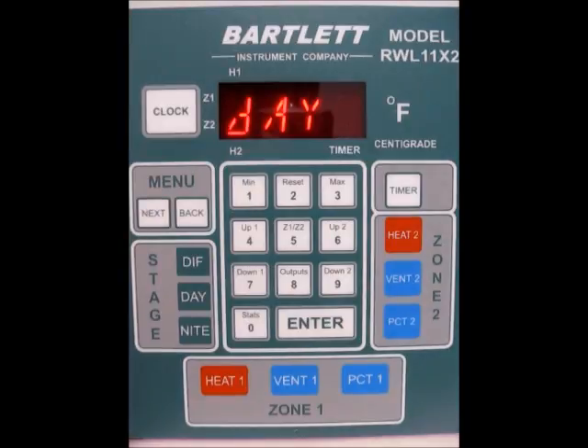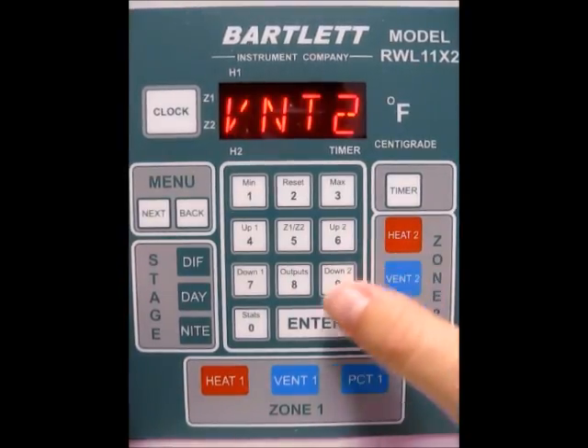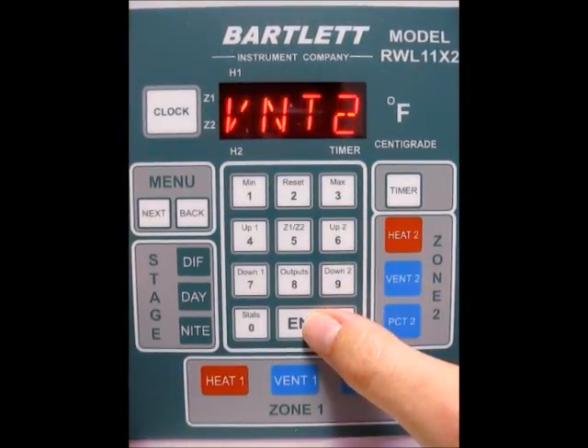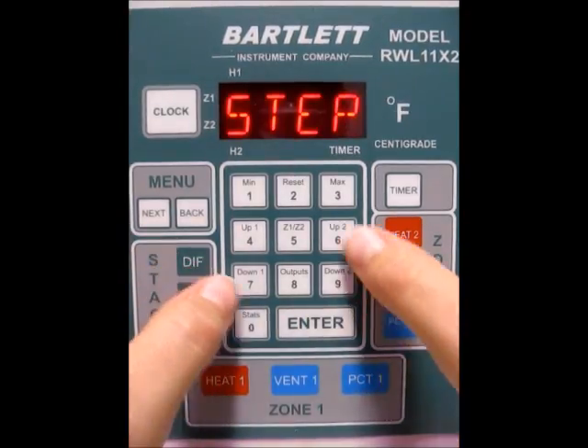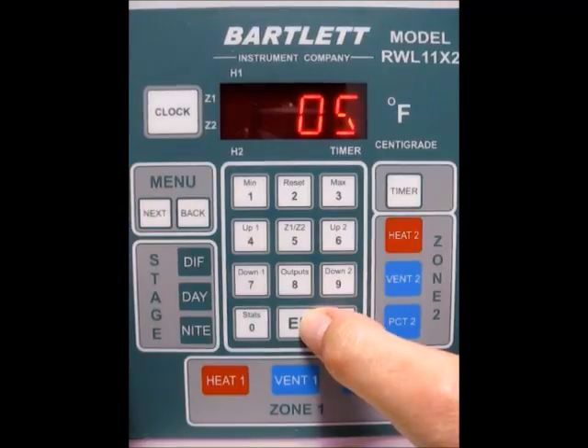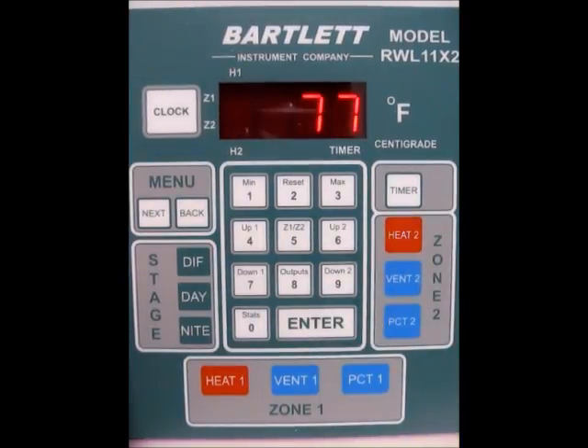So now that we've got that set, we'll go ahead and set Vent 2. So same thing with that. If it's not set to Auto, make sure it is. Press Enter. Enter your step size. So we're going to enter a step size of 5. So with our target temperature at 75, our output temperature for Vent 2 should come on at 80 degrees.